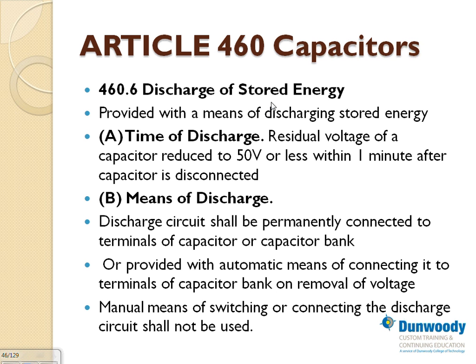So if you have low power factor, you add capacitors. We have a bank of capacitors right next to our 3000 amp, 480 switchgear, and these are always energized because of our chillers and air handling units. But with capacitors, guys, you have to have a means of discharging stored energy. Anybody get zapped by a capacitor? Be very careful with capacitors. They store energy and the bigger ones could be lethal. So they're supposed to have a means of discharging them. Within 1 minute after the capacitor has been disconnected, it should reduce the voltage to 50 volts or less. So that's the means of discharge.